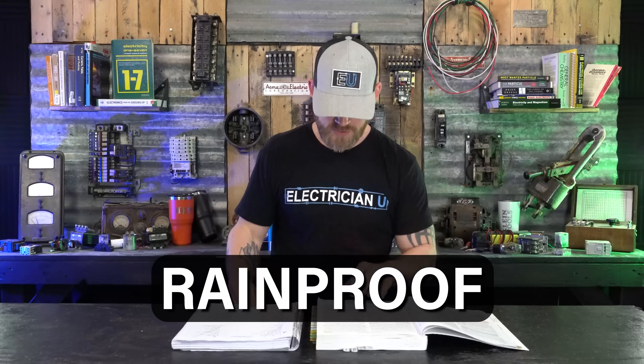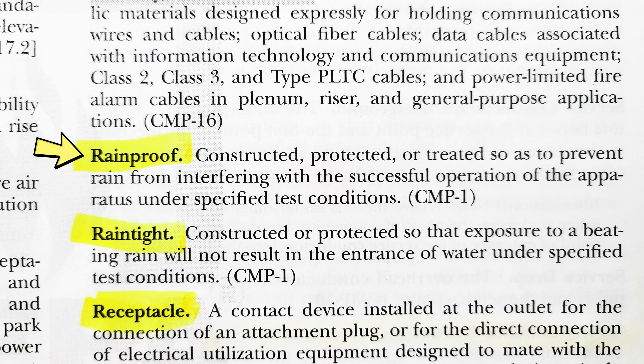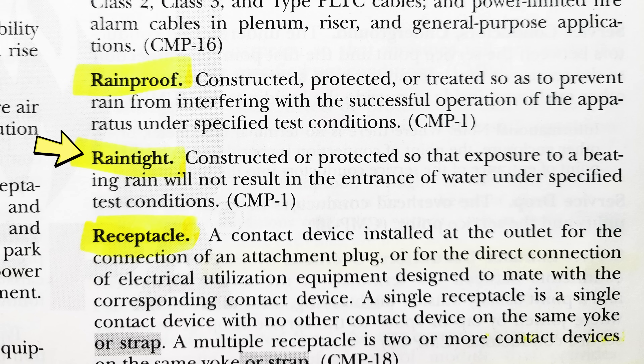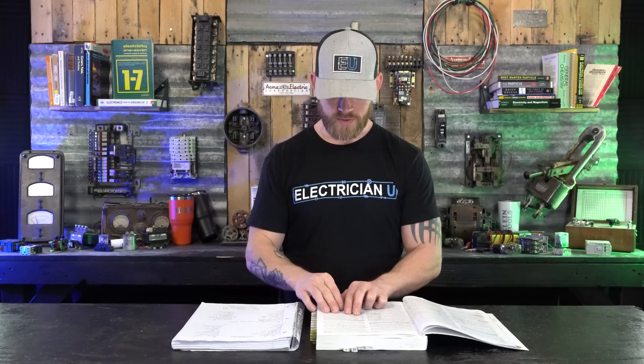Next we have rainproof. A rainproof thing is something that is constructed, protected, or treated so as to prevent rain from interfering with the successful operation of the apparatus under specified test conditions — so it's preventing rain from interfering with its operation, not preventing it from entering. Then we have raintight, which is constructed or protected so that exposure to beating rain will not result in the entrance of water under specified test conditions. So raintight means fully enclosed so beating rain can't get in, whereas rainproof is just preventing rain from interfering with the operation of the device.